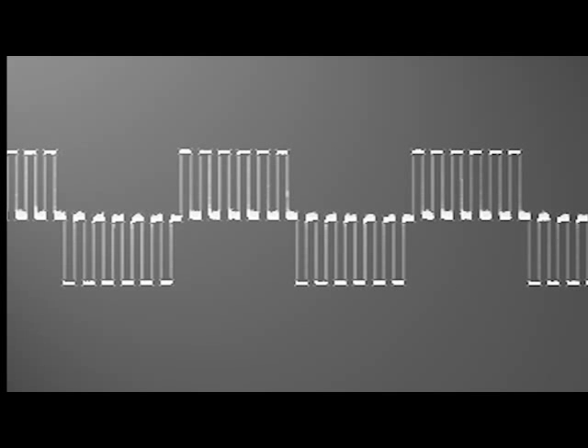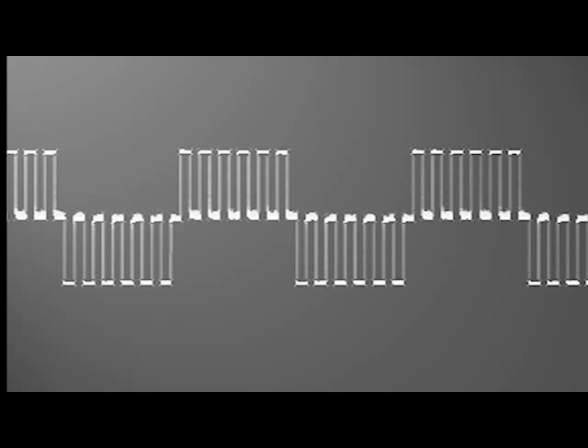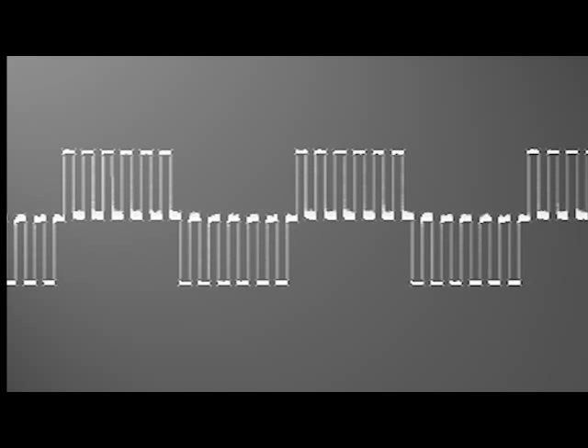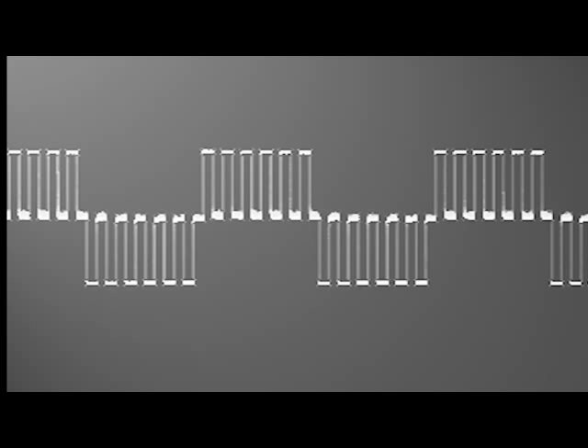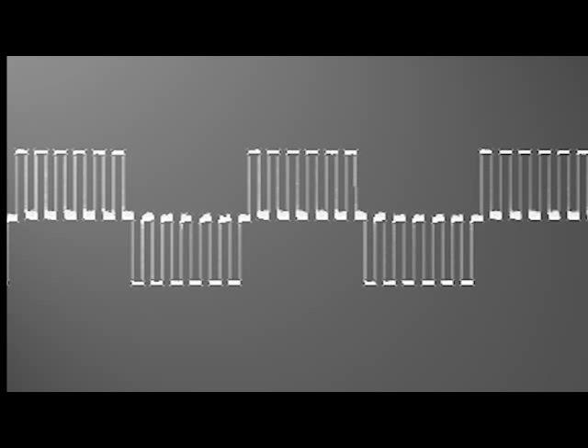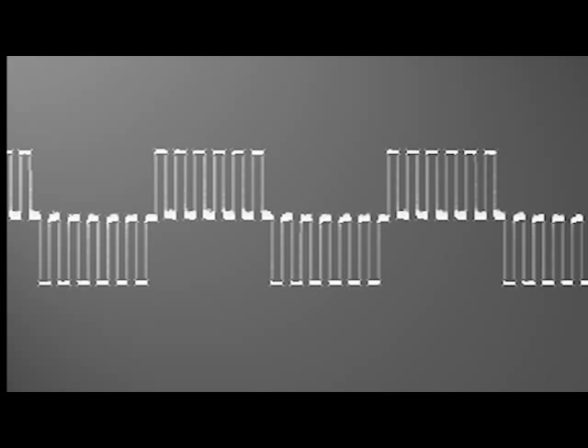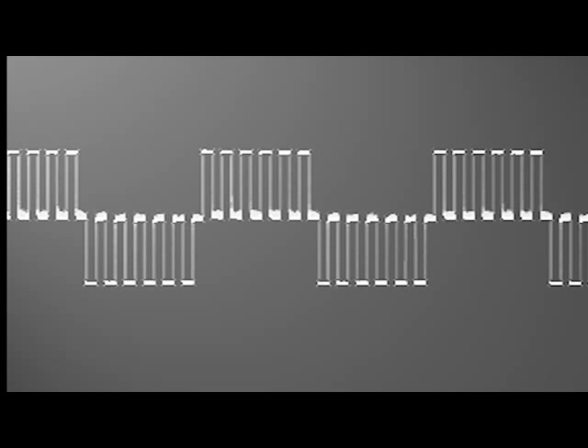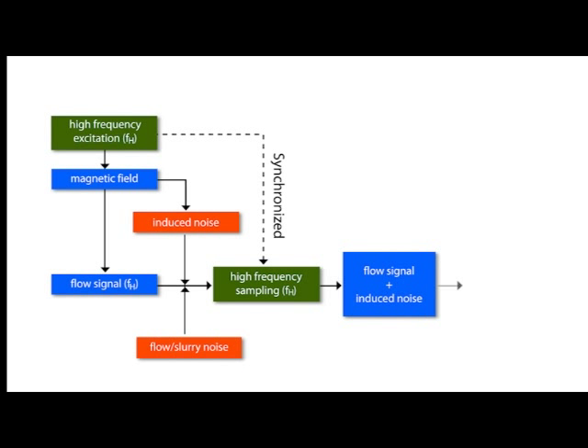Dual frequency excitation utilizes the benefits of both the high frequency and low frequency excitation methods. It has excellent zero stability from the low frequency of approximately 6 hertz, and the fast response and noise immunity from the high frequency of 75 hertz, all in one excitation method. The electrode signal is processed in parallel by a high frequency algorithm and a low frequency algorithm, the outputs of which are similar to that of an AC magmeter or DC magmeter. The slurry noise averages to zero, utilizing the output of the high frequency method.